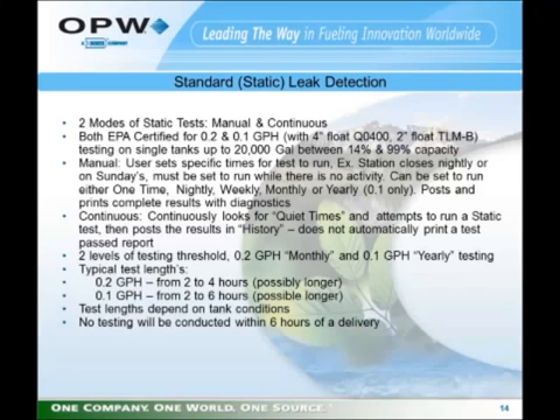The standard static leak detection is EPA certified for 0.2 gallon per hour and 0.1 gallon per hour, with both the old 4-inch floats used on the Q0400 probes or the new 2-inch floats used on the replacement for the Q0400 probe, the TLM probe. These tests are valid on single tanks only, up to 20,000 gallon capacity, when the volume is between 14% of full volume and 99% of full volume.